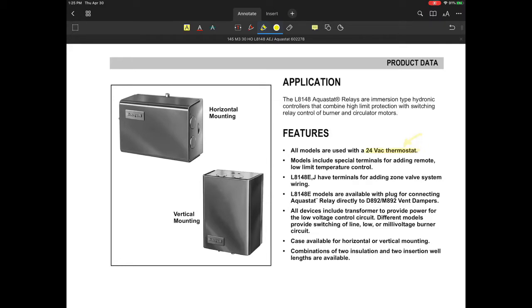Some of the models have specific types of terminals that might also allow you to have a remote, what they call a low limit temperature control. Oftentimes this low limit temperature control is a limiting temperature control that would prevent the circulator from operating in the event that boiler water was not up to temperature. The primary purpose of that is that, should you have a demand for heat, it doesn't constantly bring cold water into that boiler and put the boiler into an extended period where you would be condensing constantly in that boiler. So I would say this is really more of a pump control, as a feature, as a function.